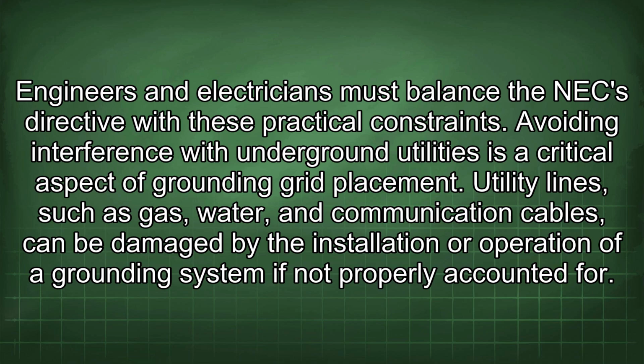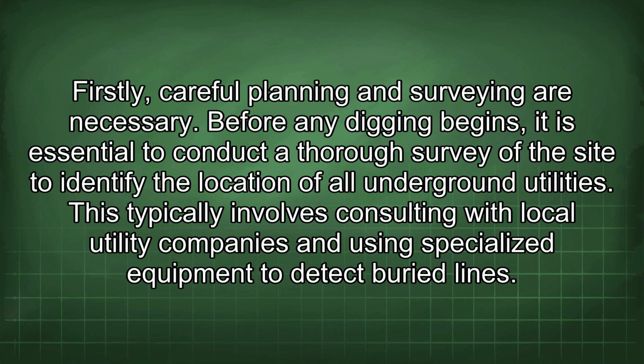Avoiding interference with underground utilities is a critical aspect of grounding grid placement. Utility lines such as gas, water, and communication cables can be damaged by the installation or operation of a grounding system if not properly accounted for. Firstly, careful planning and surveying are necessary. Before any digging begins, it is essential to conduct a thorough survey of the site to identify the location of all underground utilities. This typically involves consulting with local utility companies and using specialized equipment to detect buried lines.